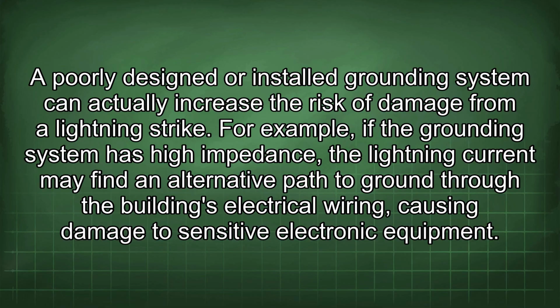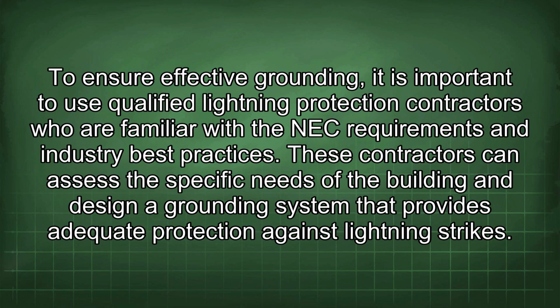For example, if the grounding system has high impedance, the lightning current may find an alternative path to ground through the building's electrical wiring, causing damage to sensitive electronic equipment. To ensure effective grounding, it is important to use qualified lightning protection contractors who are familiar with the NEC requirements and industry best practices. These contractors can assess the specific needs of the building and design a grounding system that provides adequate protection against lightning strikes.